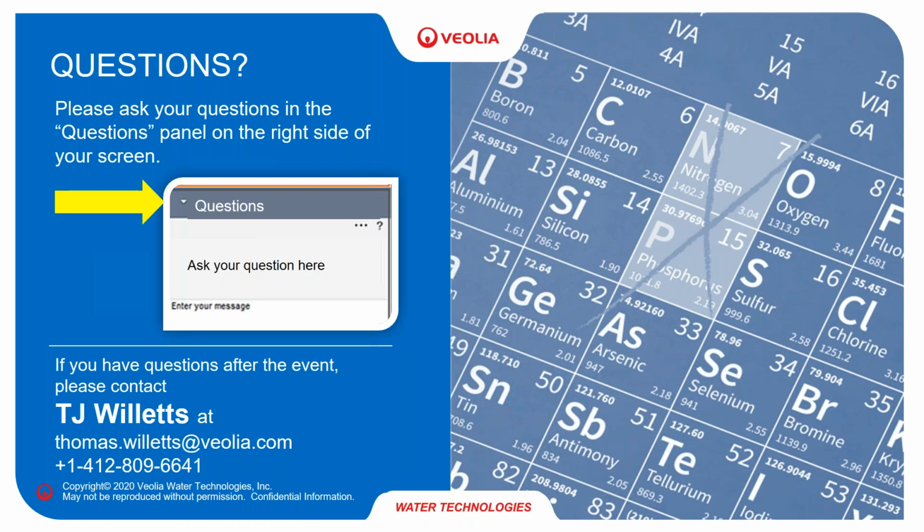I would carefully consider activated sludge for flows under 250,000 gallons per day. Actually, that's where the smallest systems start, unless there is very high solids. Active flow has been historically designed for huge municipal facilities with very large flows.